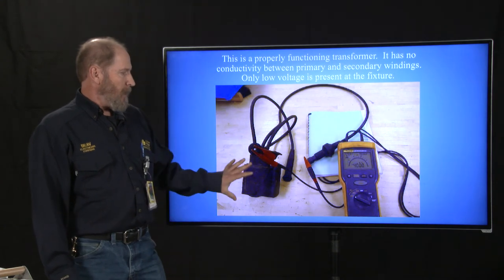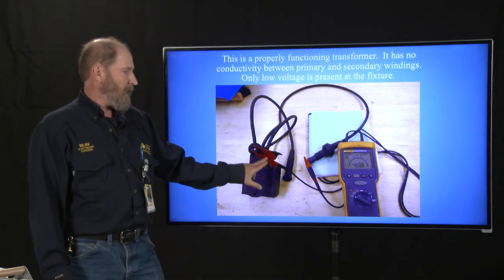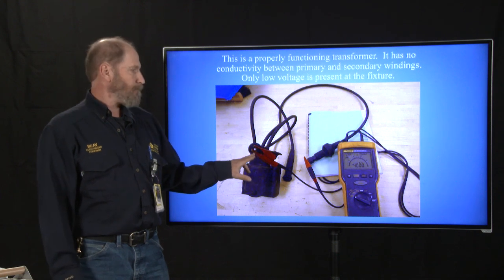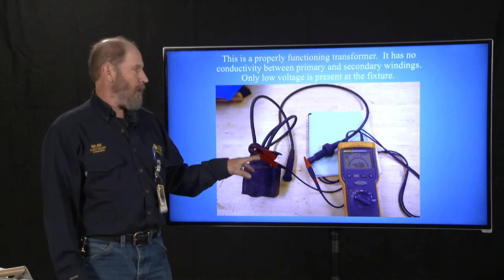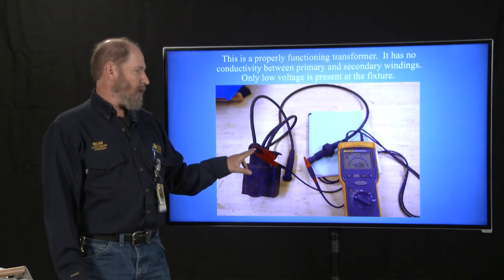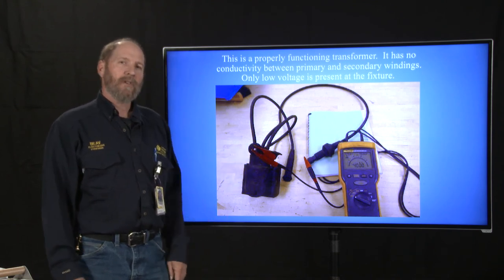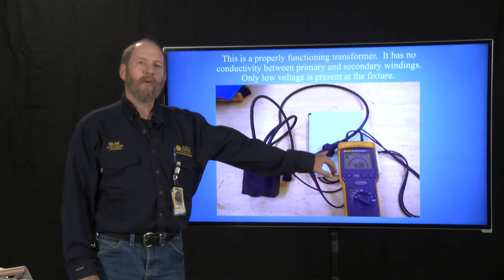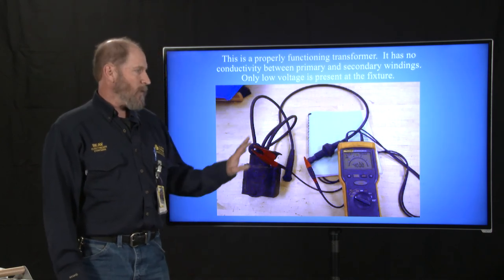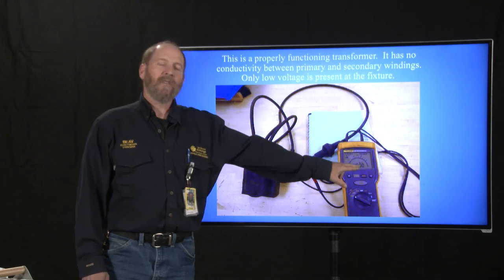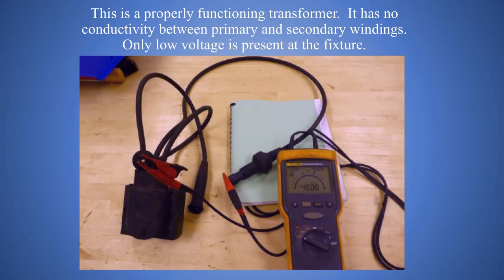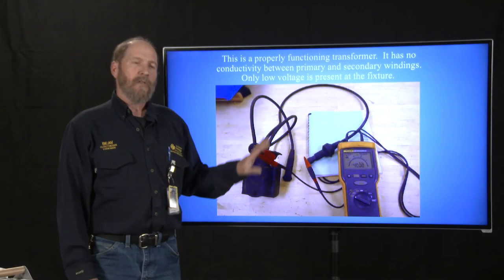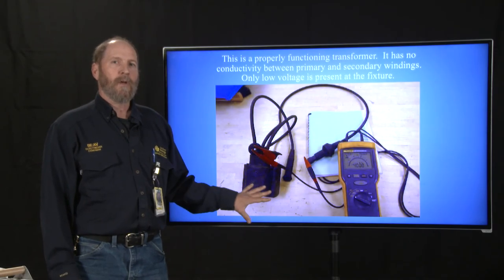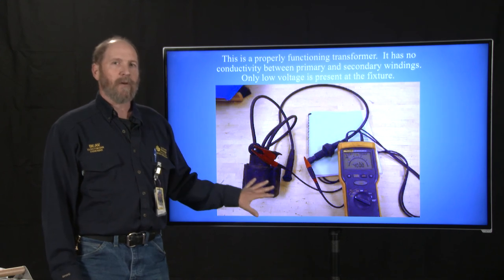So, here's an isolation transformer. What we've done is we've connected a megohmmeter to this transformer, which is going to put a 1,000-volt charge onto this transformer. We connected one end to the high voltage side of this transformer and one end to the low voltage lighting side of this transformer. We fired it up and it's maxing out this meter at 4,000 megohms. So that means there is no transfer of energy or conductivity between the high voltage coils and the low voltage coils. This is what a transformer should do. If it does anything other than this, it's a bad transformer.